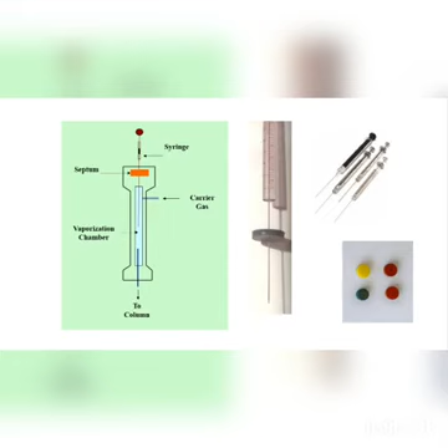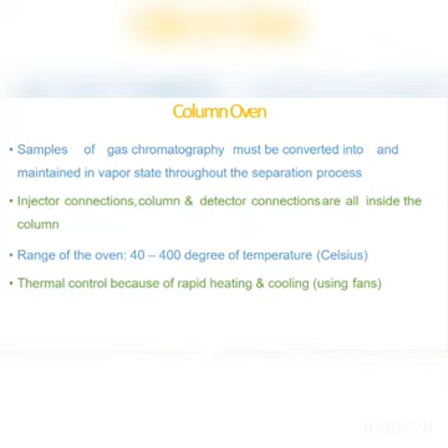Now, the column oven. The samples in gas chromatography must be converted into vapor state. So, the injector connections, column and detector connections are all inside the oven. The range of the oven is 40 to 400 degrees centigrade. For thermal control, rapid heating and cooling are used.